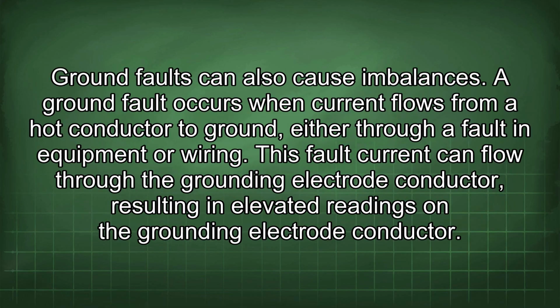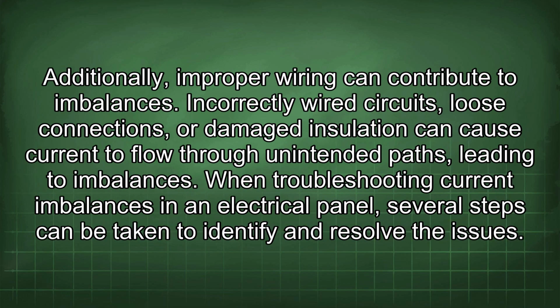Ground faults can also cause imbalances. A ground fault occurs when current flows from a hot conductor to ground, either through a fault in equipment or wiring. This fault current can flow through the grounding electrode conductor, resulting in elevated readings on the grounding electrode conductor. Additionally, improper wiring can contribute to imbalances. Incorrectly wired circuits, loose connections, or damaged insulation can cause current to flow through unintended paths, leading to imbalances.